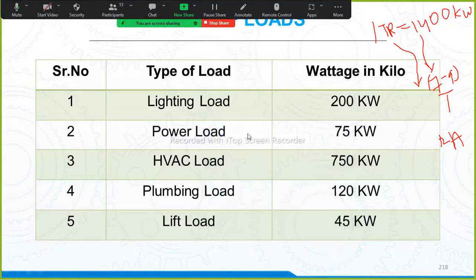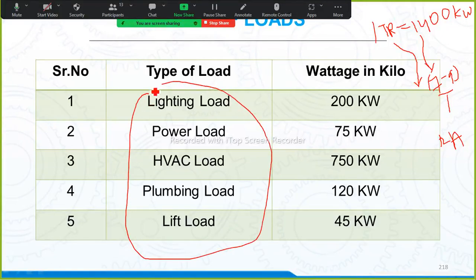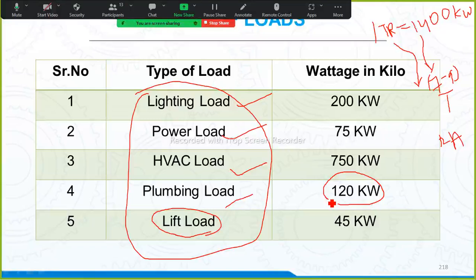So now, in your motors also, in your category here also, we have types of loads. Lighting load is not an inductive load, power load is not an inductive load. HVAC load, this is centralized air conditioning. Now, purely squirrel cage induction motor is nothing but your plumbing load. Why? Lift load, they might be using a DC motor, but in your given loads, the purely squirrel cage induction motor is nothing but your water motor and a firefighting motor. So when you check the conditions, we need to check based upon the mostly used plumbing load only, because in the plumbing the mostly loads are purely squirrel cage induction motors.